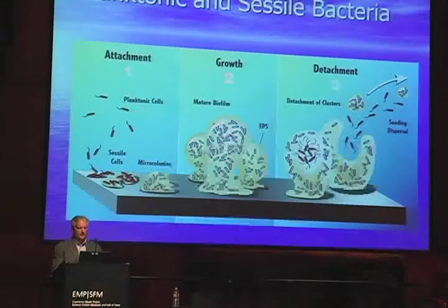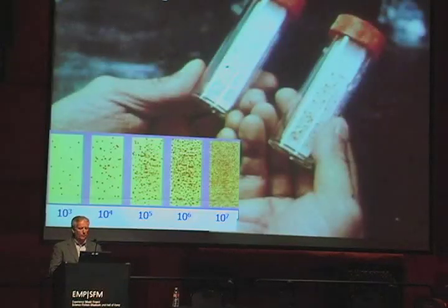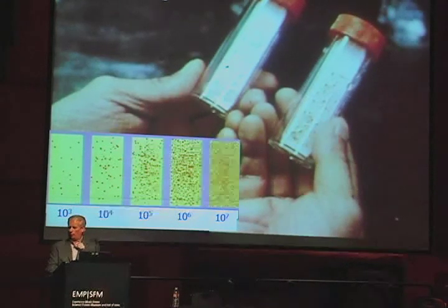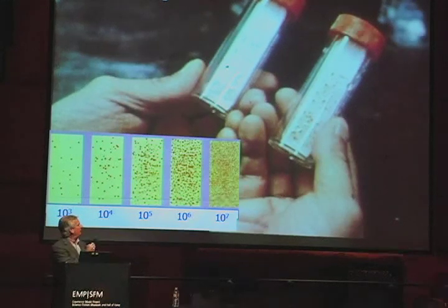So just be aware that just because you measure biological activity with bacteria strips doesn't mean you have a good and healthy system. Probably the best way from a field perspective to measure bacteria is through dip slides. You've probably seen the Hawk dip slides or the Orion dip slides. Basically, they have an agar nutrient solution on the paddle itself.